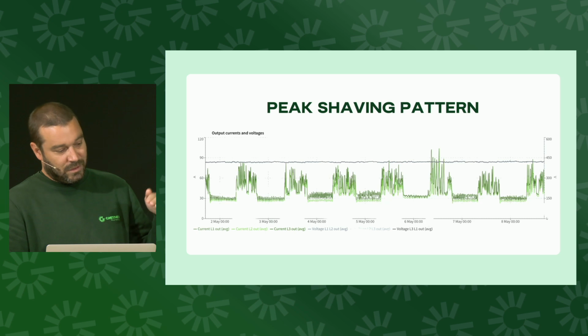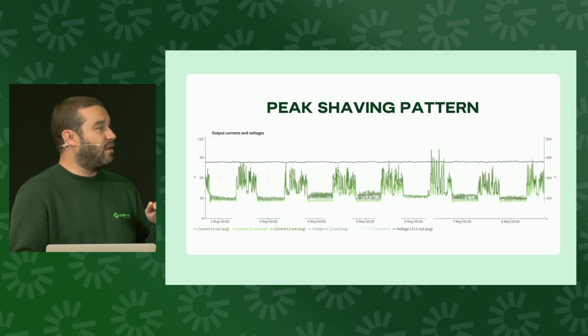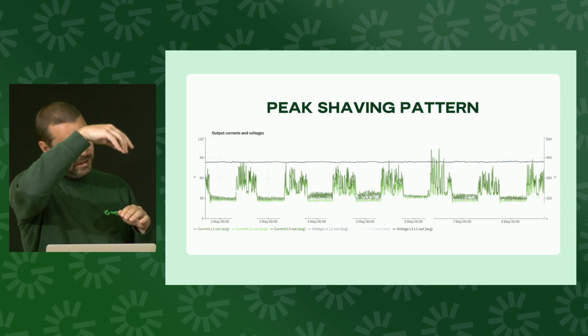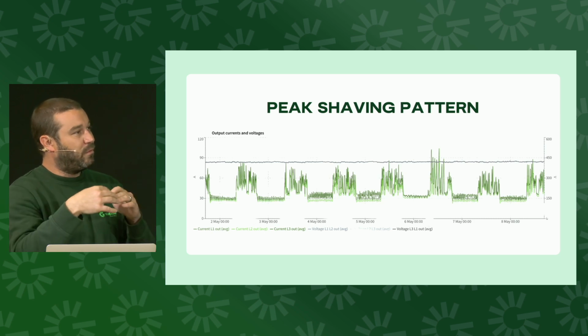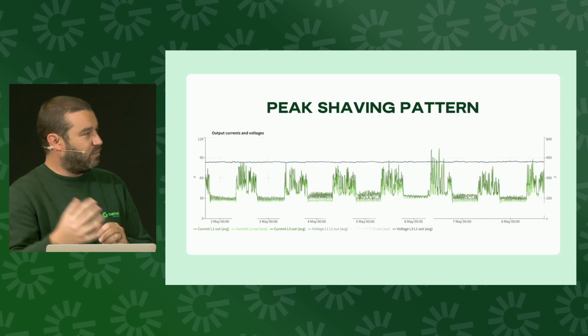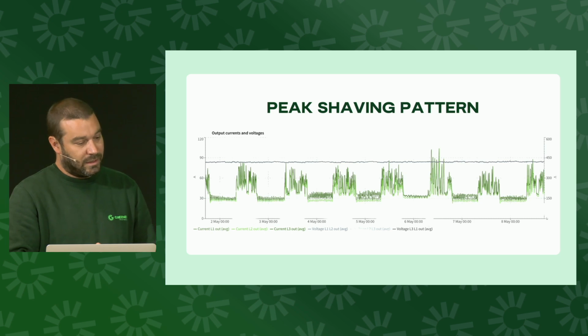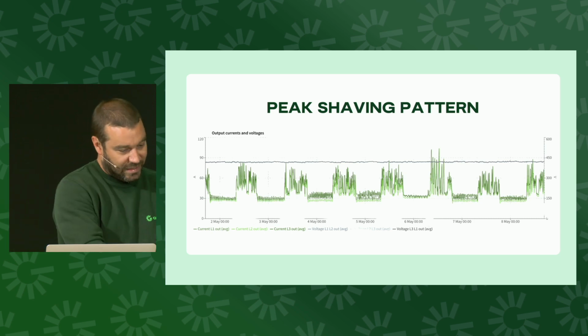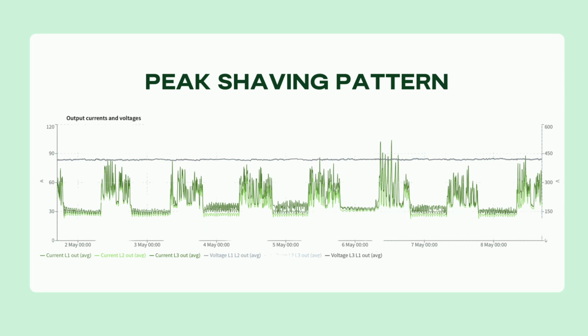So we have a small power grid connection coming in, and then we, again, as Robin explained, stack the inverter on top of or in parallel with that, which then means we have the peak power available to come in. Also through the data gathered, you can see here, this was a week's worth of data from both scanners running simultaneously. And although it is exceeding the 63 amp mark, it never goes anywhere near the potential 600 that we were initially tasked with.